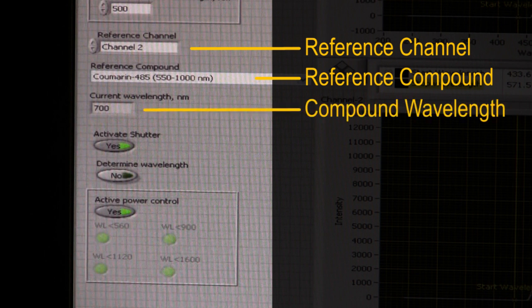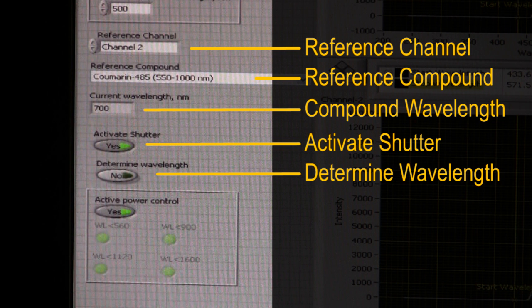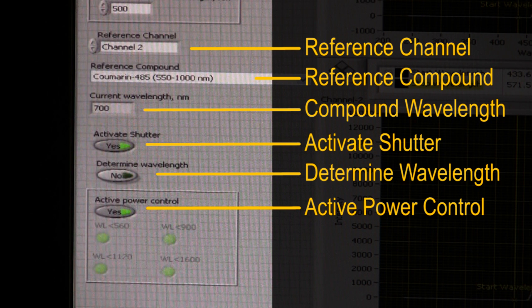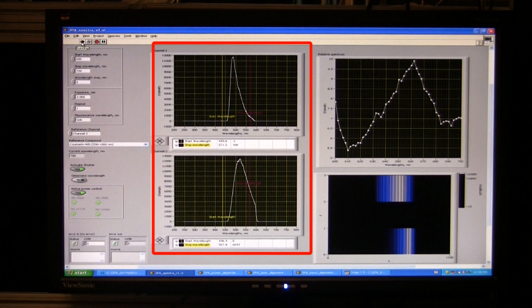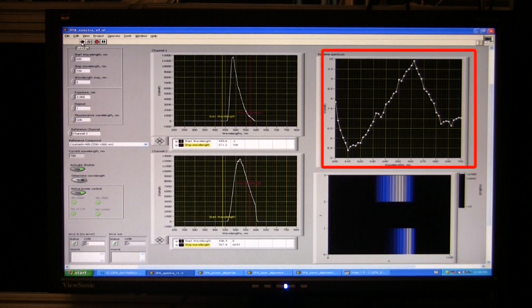Over here it shows the current wavelengths at which laser is sitting. And then there are some buttons allowing us to activate or disable shutter during measurements, to determine wavelengths at each step or disable this determination, and to actively control power of the excitation laser or skip that part. Those two graphs show fluorescence spectra of compounds sitting in channel 1 and channel 2. This graph over here shows us actual image of the CCD beamed together, such that this is everything what is getting out of channel 1, and this is everything getting out of channel 2. And finally this graph over here shows us the real spectrum measured during this experiment.